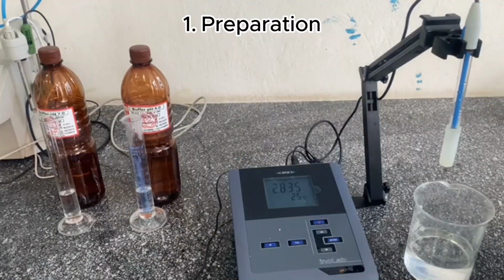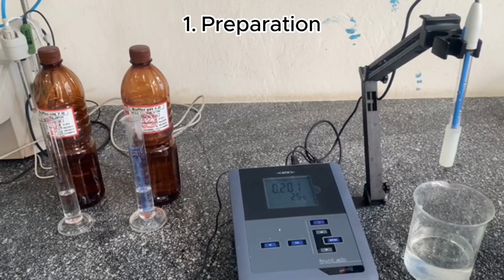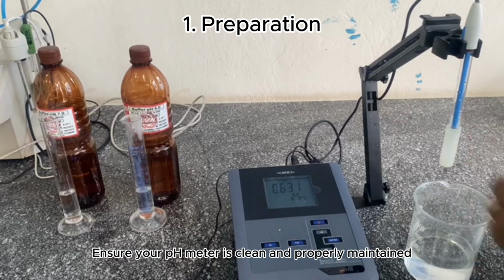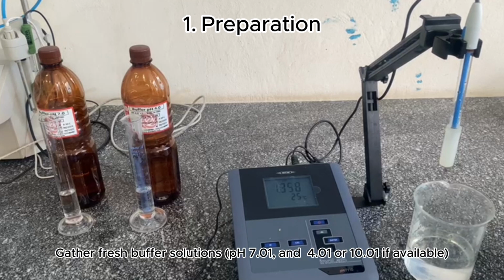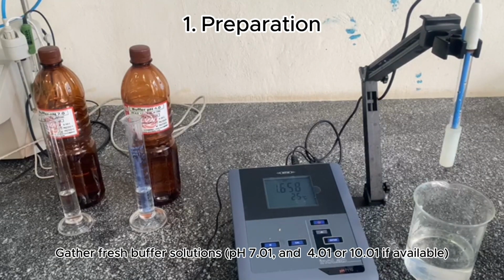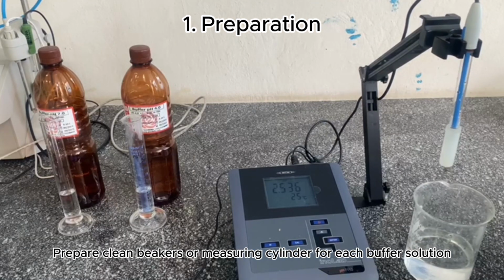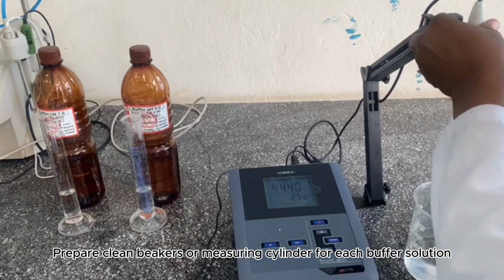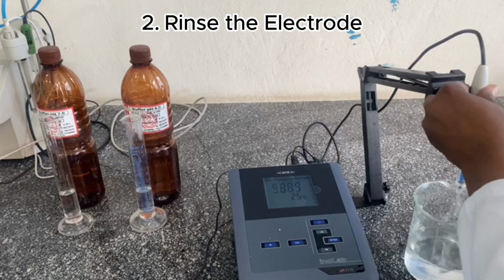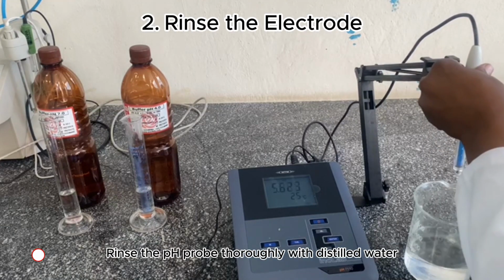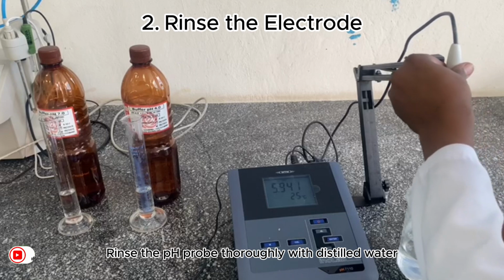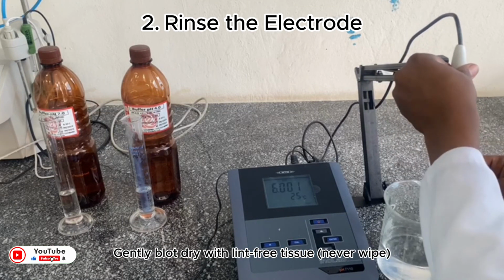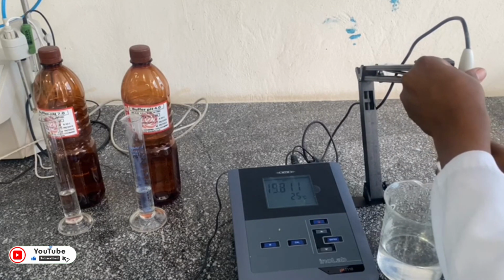Proper pH meter calibration procedure. 1. Preparation. Ensure your pH meter is clean and properly maintained. Gather fresh buffer solutions, pH 7.01, and 4.01 or 10.01 if available. Prepare clean beakers or measuring cylinder for each buffer solution. 2. Rinse the electrode. Rinse the pH probe thoroughly with distilled water. Gently blot dry with lint-free tissue, never wipe.